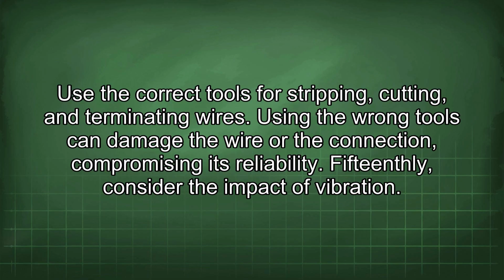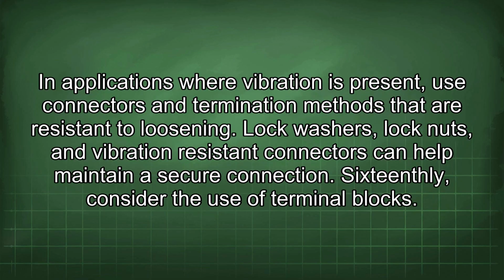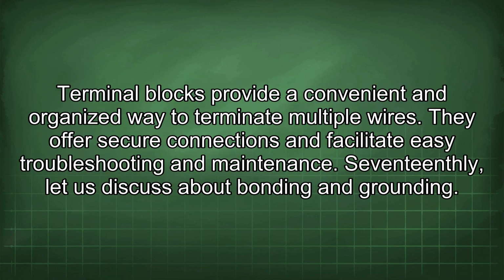15thly, consider the impact of vibration. In applications where vibration is present, use connectors and termination methods that are resistant to loosening. Lock washers, lock nuts, and vibration-resistant connectors can help maintain a secure connection. 16thly, consider the use of terminal blocks. Terminal blocks provide a convenient and organized way to terminate multiple wires. They offer secure connections and facilitate easy troubleshooting and maintenance.